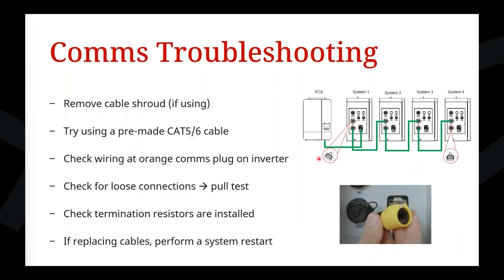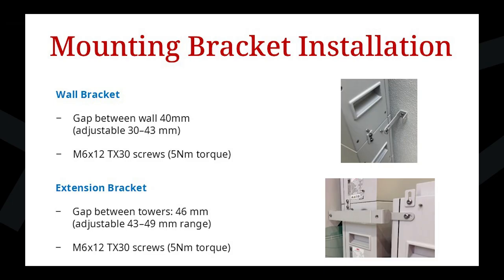So there are RJ45 plugs, as you can see here. If you've got multiple battery towers, it should be installed on the in port of the first battery tower and the out port of the last battery tower. If you only have one tower, then they should be on both in and out ports. And just note, if you are replacing cables, particularly those running between multiple towers, make sure that you do a whole system restart after you've replaced those cables.